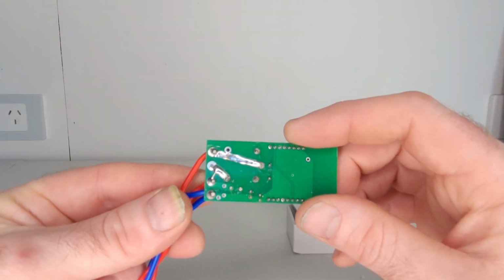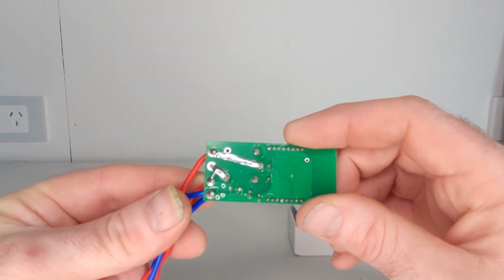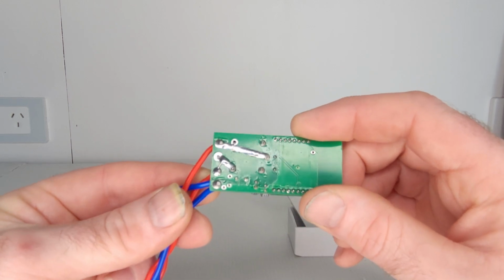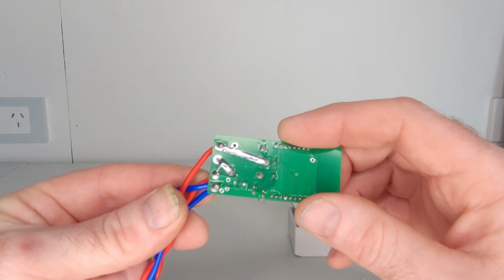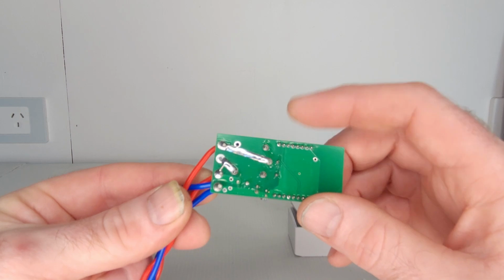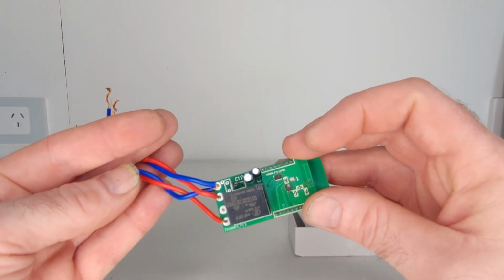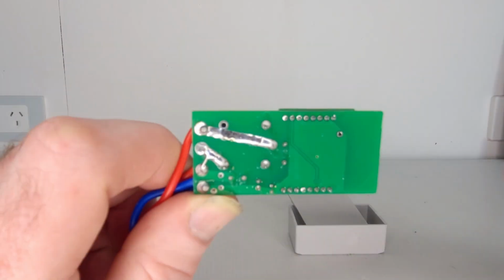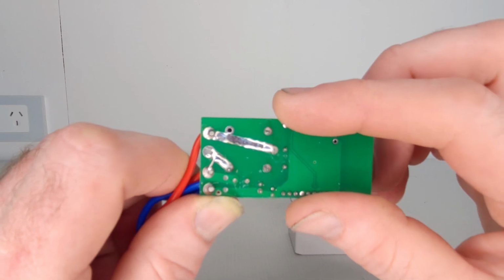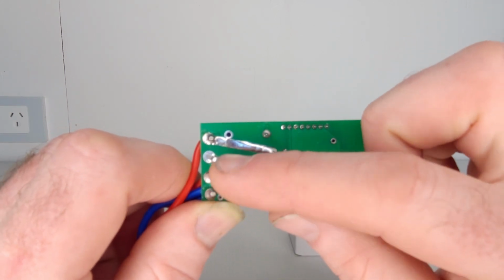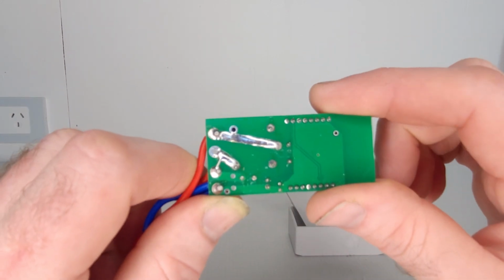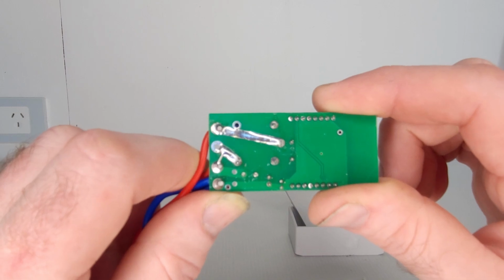This switch is a wet contact design, meaning that when the relay is triggered, there will be a voltage supplied to the output, and the output voltage is the same as the input voltage. So for this particular switch, that's 12 volts DC. Of course, the output can be set up as dry contact as well by simply removing this little link here. So as I said before, you may need to modify the switch to suit your needs.